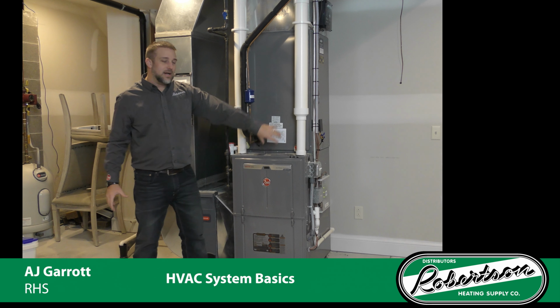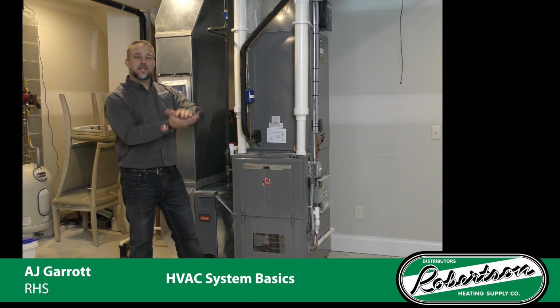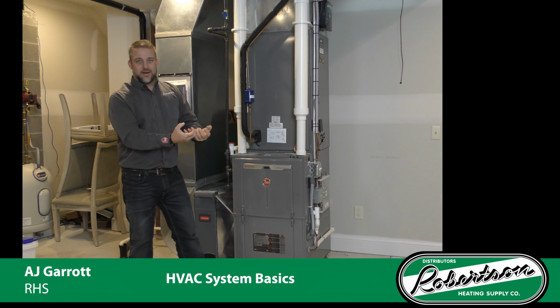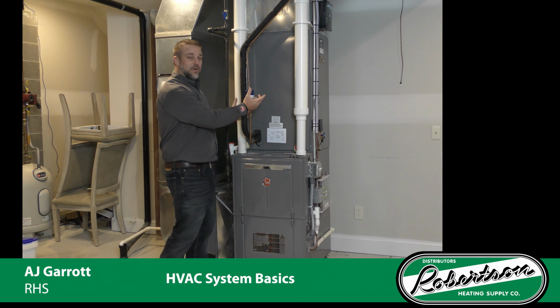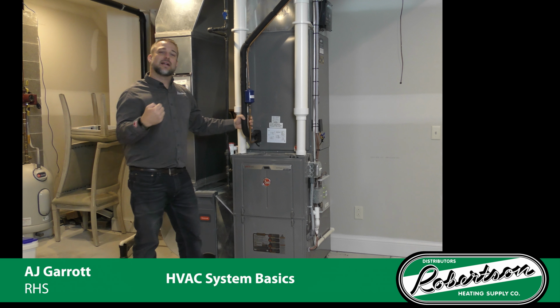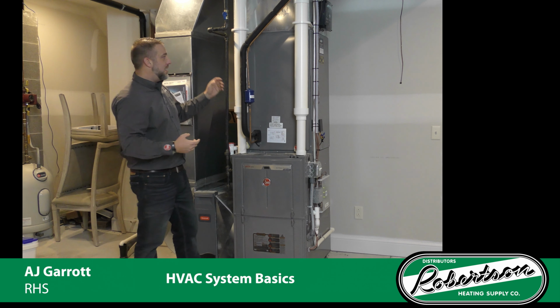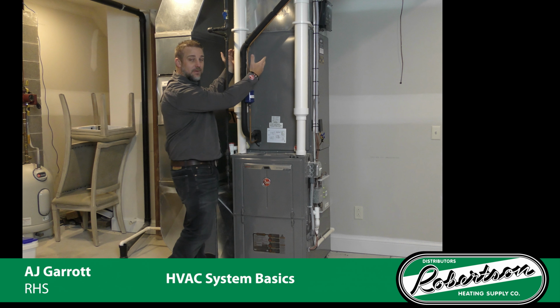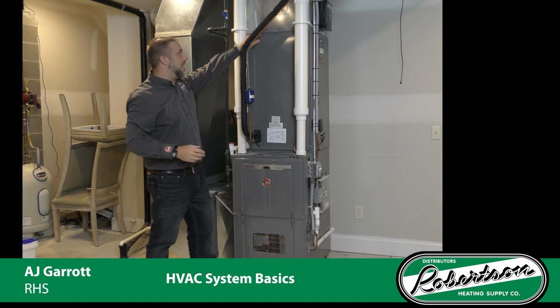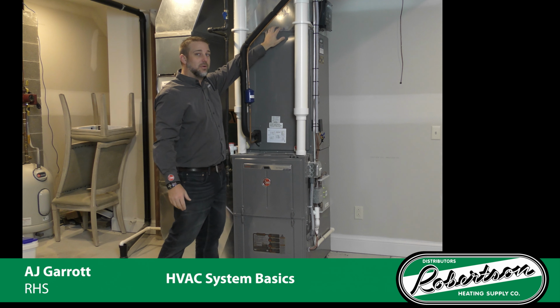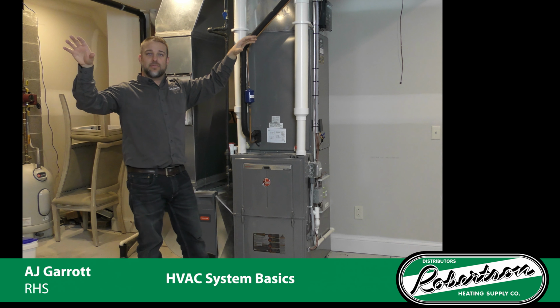So the 70 degree return air touching that 45 degree evaporator coil is going to cool the air down and warm the refrigerant up because it's extracting heat out of the air. After the air passes through the evaporator coil, it is then cooled down inside the plenum up here and then distributed throughout the building.